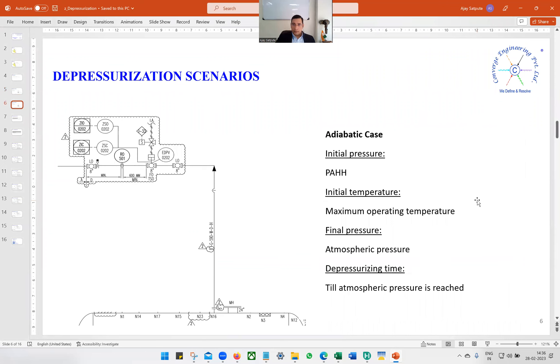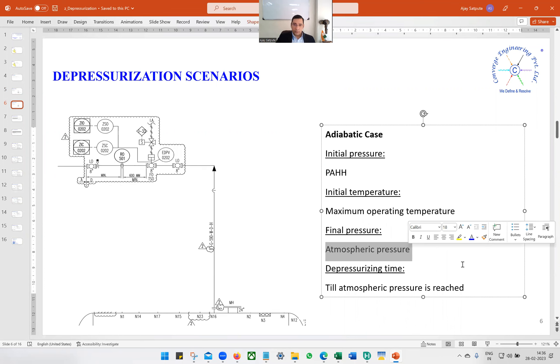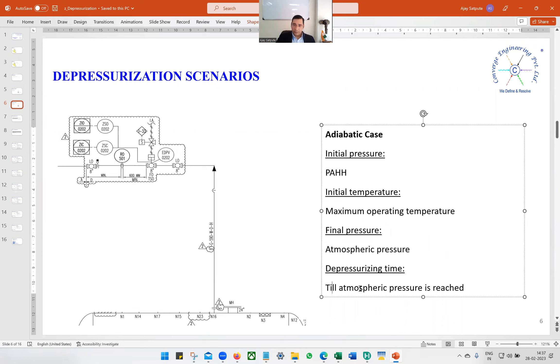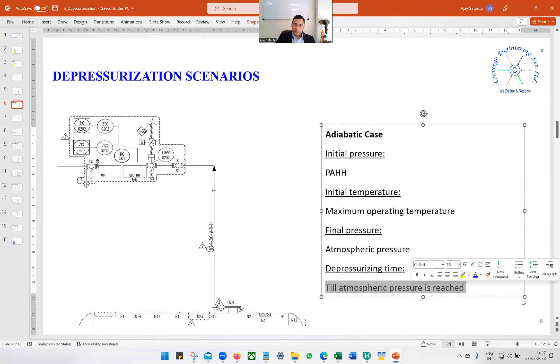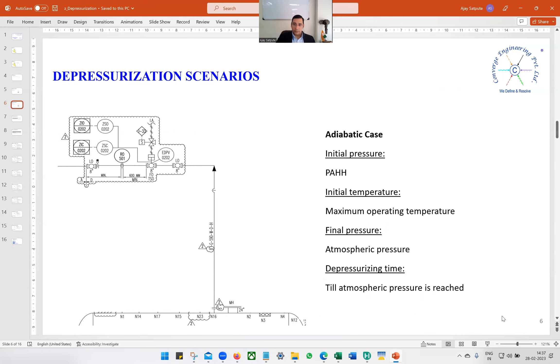There is another scenario — the adiabatic case. Here the initial pressure is PAHH, initial temperature is maximum operating temperature, and final pressure is atmospheric pressure. Unlike the fire case, we are not in a hurry. We can continue until we reach atmospheric pressure, so it could take a couple of hours — that is not a problem.